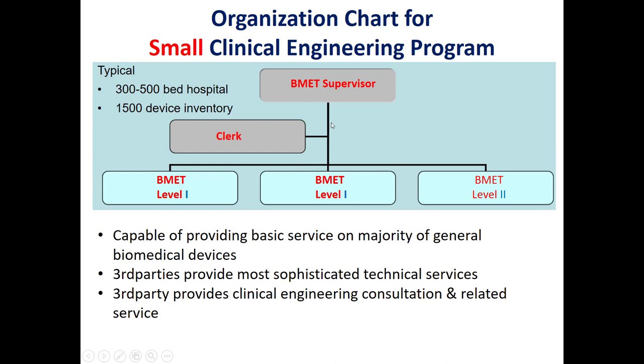Here we see an organizational chart for a small clinical engineering department, suitable for a hospital with 300 to 500 bed capacity or a medical device inventory of more than 1,500 devices. Such a department provides basic services for the majority of general biomedical devices, while more sophisticated technical services and clinical engineering consultation are covered by third parties. The structure includes a head of department, a BMET supervisor, biomedical technicians at level one and two, and a clerk.